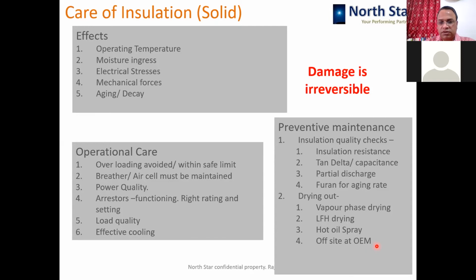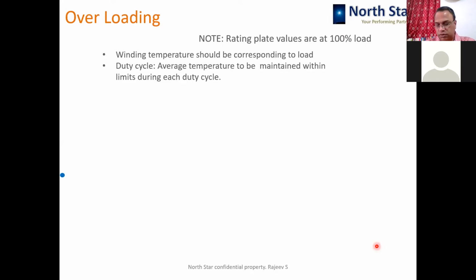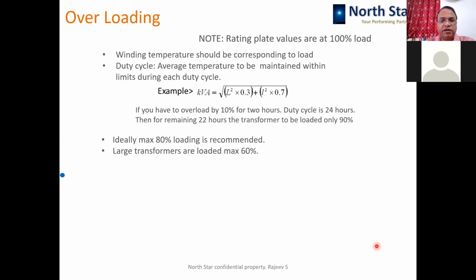So this is about the solid insulation. Then overloading also affects the quality of the solid insulation. The temperature limits given on the rating plate are at 100% load. So when you are setting your OTIs and WTIs, you should consider your loading, and you can decide your own alarm and trip settings for these devices, not always at the rating plate values. Your winding temperature setting should correspond to the load.